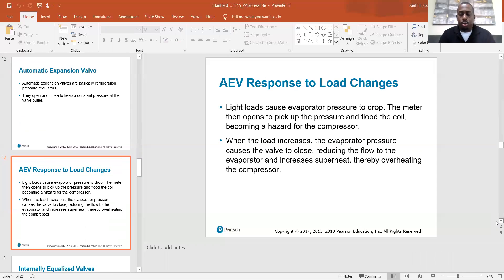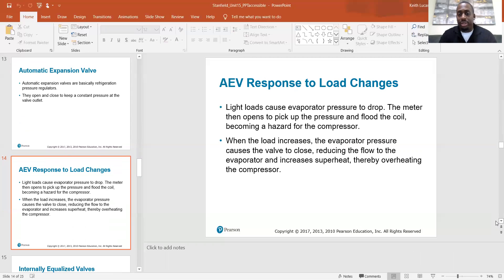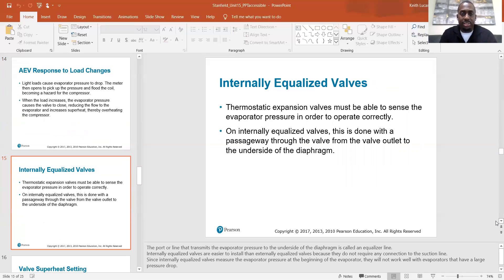Regarding AEV response to load changes: light loads cause evaporator pressure to drop, and the metering device then opens to pick up the pressure, which can flood the coil and become a hazard for the compressor. When the load increases, the higher evaporator pressure causes the valve to close, reducing refrigerant flow to the evaporator and increasing superheat, which can overheat the compressor. You have to be careful not to overshoot it in either direction.